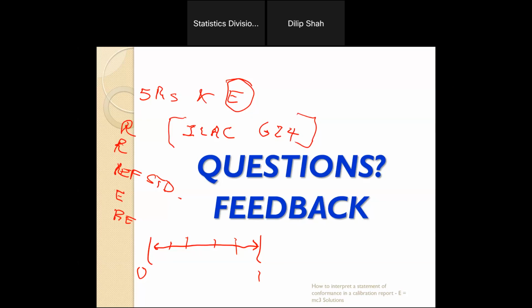Now, this document is under review, but the one that is current, that came out in 2007, is still excellent. And the reason it's under review is the 17025 standard got revised, and they're going to, I think, revise the references to the new standard in there. But it is still a good document. So when you go to that ILAC website, look for the ILAC G24 document, and that talks a lot about the calibration interval. They've got like 5 approaches, and they do a nice job.